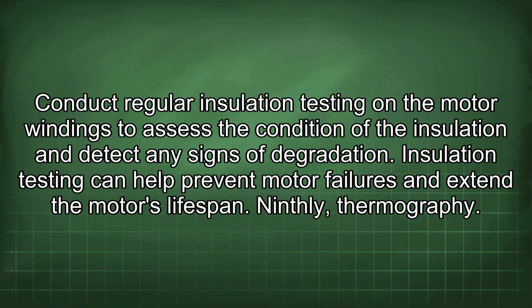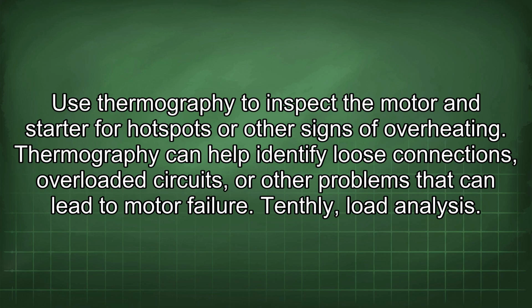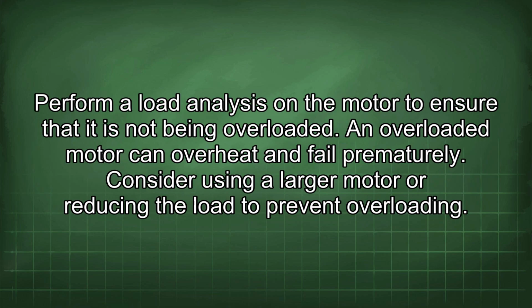Ninthly, thermography. Use thermography to inspect the motor and starter for hotspots or other signs of overheating. Thermography can help identify loose connections, overloaded circuits, or other problems that can lead to motor failure. Tenthly, load analysis. Perform a load analysis on the motor to ensure that it is not being overloaded. An overloaded motor can overheat and fail prematurely. Consider using a larger motor or reducing the load to prevent overloading.